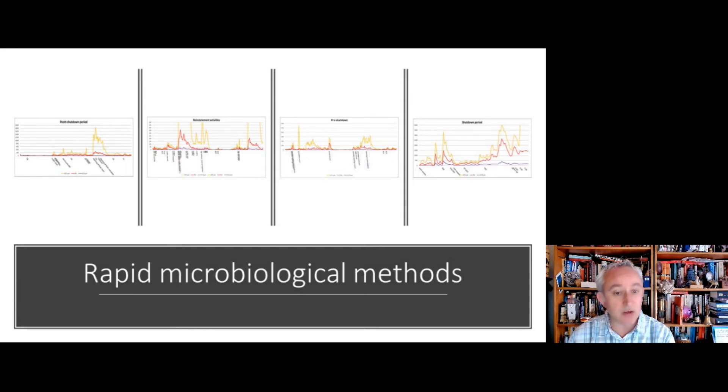So we've got things like conditions before shutdown, conditions during a shutdown including a point when the HVAC system is deactivated, the reinstatement of the clean room and the cleaning activities, and the amount of time that's required for the clean room to settle down after coming through these series of steps to get back to its original state.